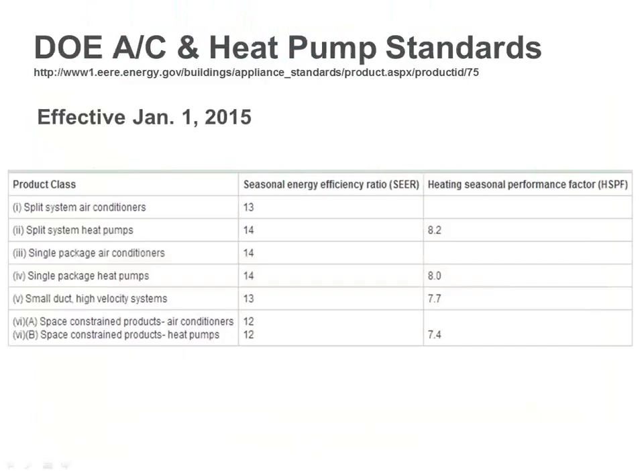Another way that we improve the efficiency of overall buildings is by increasing the minimum product efficiencies of certain things. The next major one that relates to HVAC is the Department of Energy changes for air conditioners and heat pumps. If you are in the Midwest, the split system air conditioner stays at 13 SEER, and that's the majority of what you all do. However, the heat pump split systems do change. The new minimum is 14 SEER for a heat pump and 8.2 HSPF, heating seasonal performance factor.